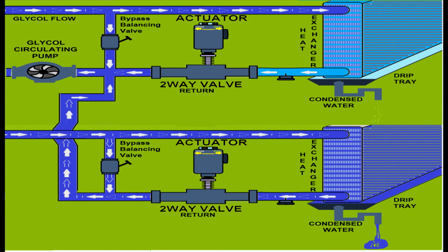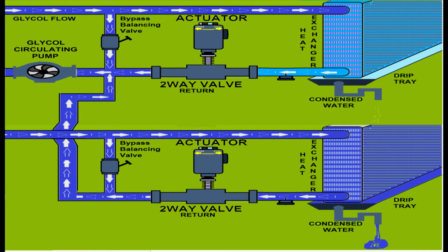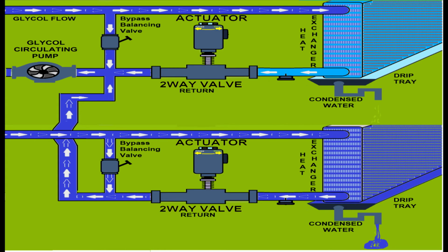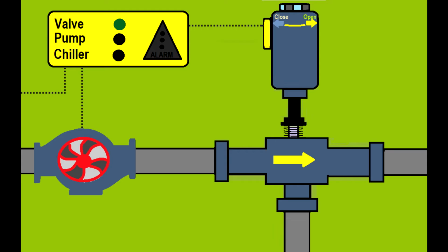There should be a differential between flow and return on a temperature. If you allow more glycol to pass by because the system is unbalanced, you might not have the required delta T, and then your system will be inefficient. Also, we know that for a glycol, for a cooling agent or heating agent to run through a pipe, the pump must run. Even if you act onto the actuator and open and close the valve, the heating or cooling agent will not move through the system if the pump is not running.